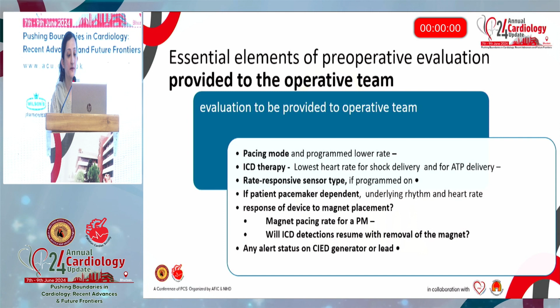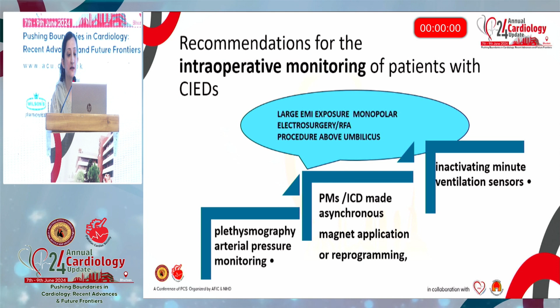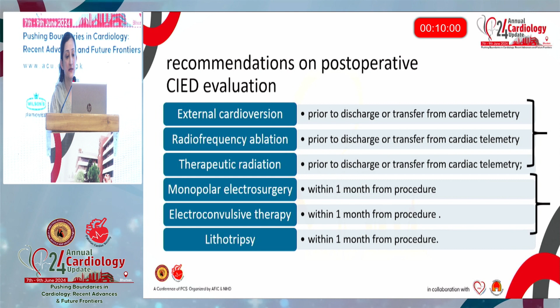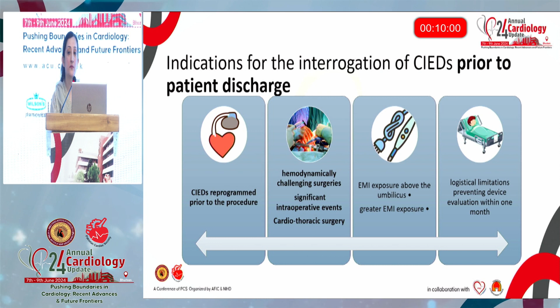During the intraoperative procedure, patients with ICDs and pacemakers with large electromagnetic exposure to monopolar electrosurgery or RFA in procedures above the umbilicus should be turned to asynchronous mode. The device should be re-evaluated prior to discharge in cardioversion, radiofrequency ablations, and therapeutic radiations, and after a month in monopolar electrosurgery, ECT, and lithotripsy. Also if the device was reprogrammed before the procedure, if there was a hemodynamically challenging procedure, if large exposure to EMI occurred, and if there are logistic problems limiting the patient follow-up within a month.